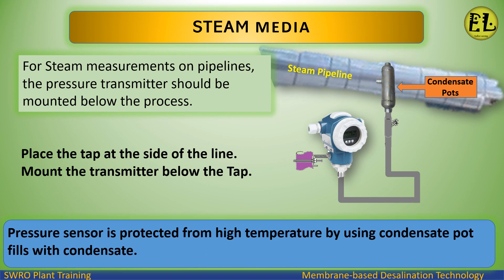Steam Media: For steam measurements on pipelines, the pressure transmitter should be mounted below the process. Place the tap at the side of the line and mount the transmitter below the tap. The pressure sensor is protected from high temperature by using a condensate pot filled with condensate.